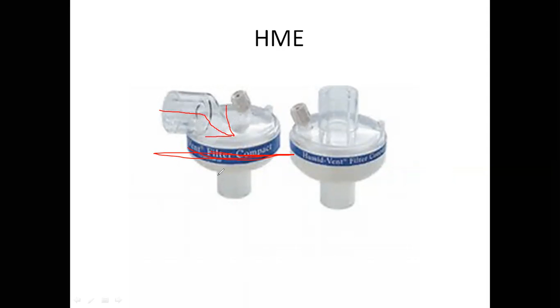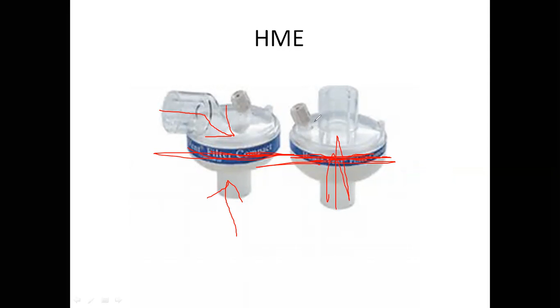So if we go back to my lousy drawing, this is kind of the line of demarcation. We have the cold gas coming in from the ventilator, and we have the heated gas on this side, and this membrane allows the gas to pass, but does not allow the humidified gas to get dried out by the cold, dry gas coming in from the vent. And typically, most hospitals start with these because a non-heated circuit is less expensive. And the HME manufacturers will say that they're just as good.